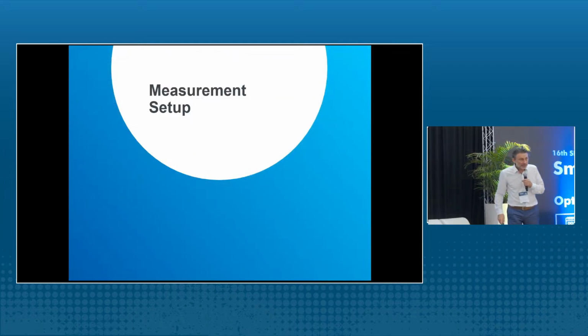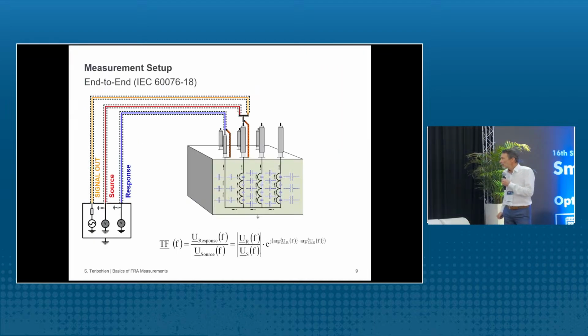Let's come to the measurement setup. How do I measure the frequency spectrum of a full winding? Normally this is done with a so-called end-to-end measurement, because of course you have access to the winding only at the ends of the winding. Yeah, because the winding is in the transformer tank filled with oil, so you cannot measure somewhere in between. Just the ends of the winding are brought to the bushings, so you can connect your measuring system to the bushings. Yeah, we have now here the measuring equipment.